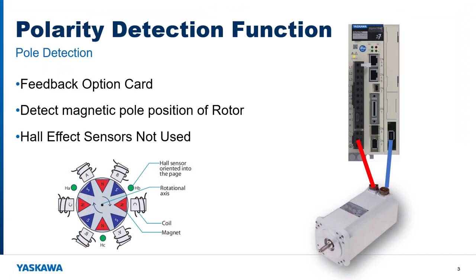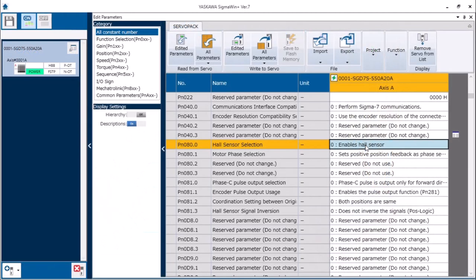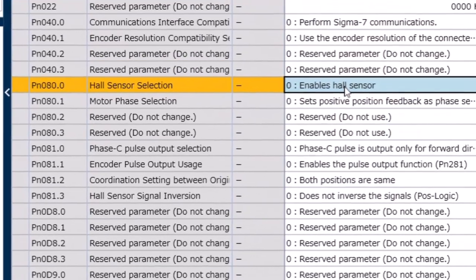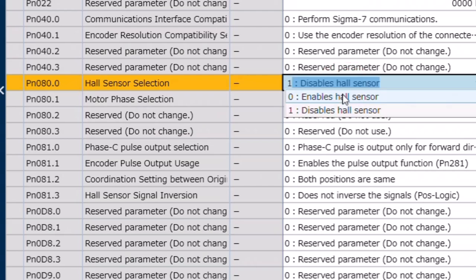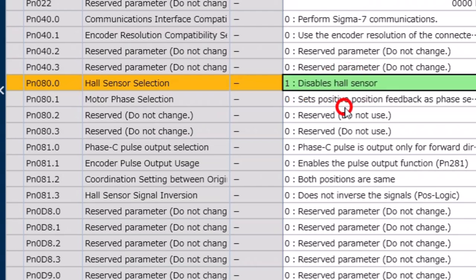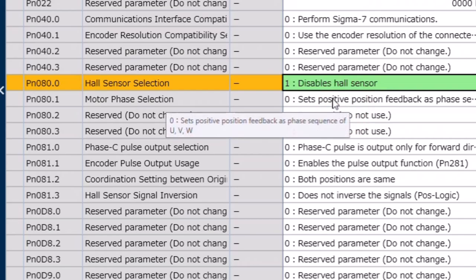Some motors use hall sensors to detect the position of the magnetic poles as is selected by default in parameter PN080. These motors don't need hall sensors so we need to disable with setting 1.